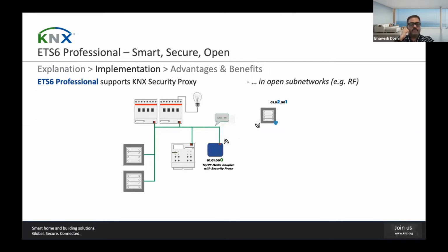Right. So the first use case addresses the commonly used scenario where an existing KNX TP installation shall be extended with KNX RF S-mode devices behind the media coupler, in contrast to twisted pair cable that is buried inside concrete walls and thereby provides a basic security against outside attackers. The KNX RF wireless spectrum is an open medium that can easily be accessed anonymously from outside the installation. Therefore, it is a legitimate requirement to secure all communications within this KNX RF subnetwork.